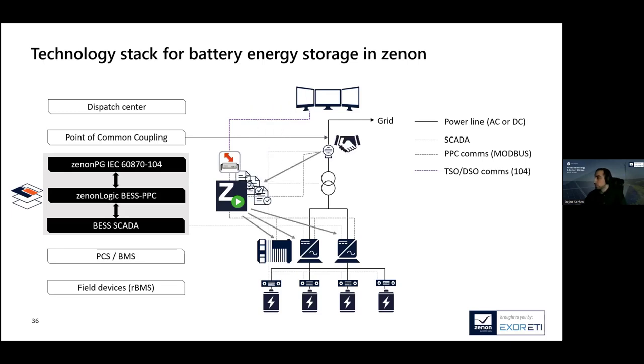As for protocols, you have already heard about the standard energy protocols which are included with Zenon drivers. Additionally, protocols that are typically necessary in battery storage systems are Controller Area Network, so CAN. If we also need to take care of cooling and heating of our battery banks, we need a protocol that is used in HVAC systems, and that is our Zenon KNX driver, plus MQTT drivers if we want to communicate through IoT protocols.